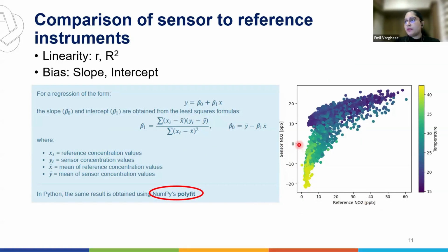Ideally, it should be passing through the 1:1 line if the two are highly correlated to each other. And then here we are coloring these markers with temperature, which in the case of NO2 can be one of the meteorological factors which can affect its performance. From this plot itself, we identify that when the temperature is very high, the sensor is reporting negative values, while when the temperature is very low, or below 25, the values are almost on the 1:1 line.